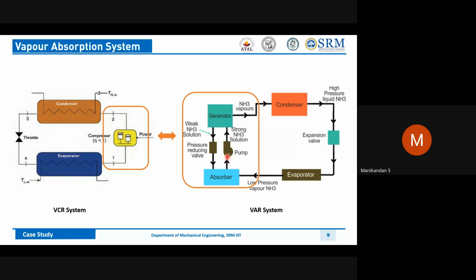We have a generator. The vapor coming out of the evaporator is absorbed by the liquid absorbent. Since it is a liquid, we use a pump to send it to the generator. The generator, as its name suggests, takes some amount of heat and generates the refrigerant vapor.